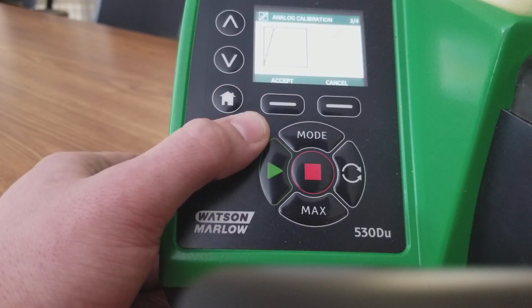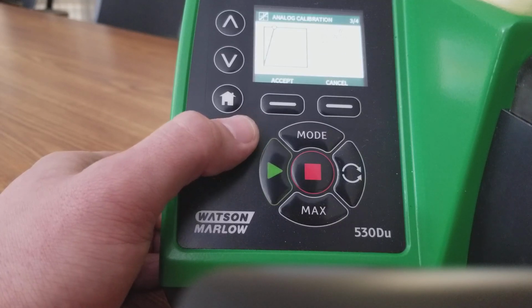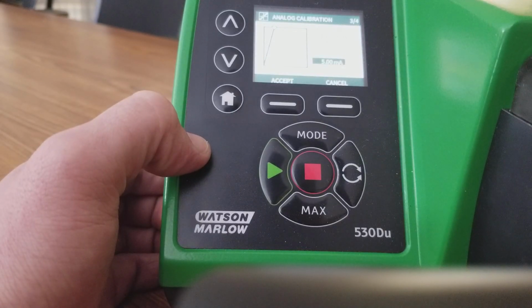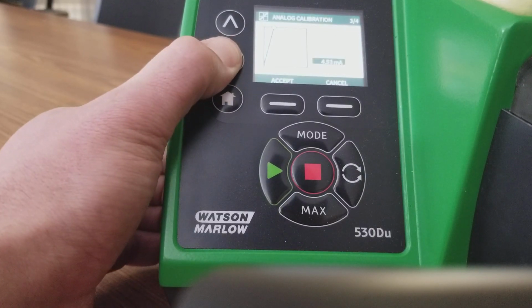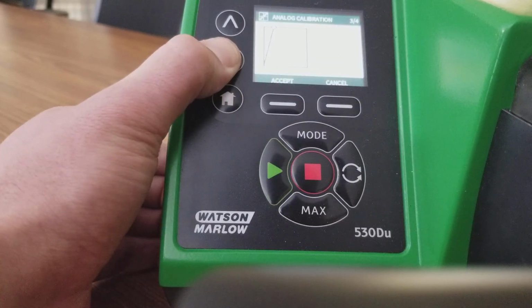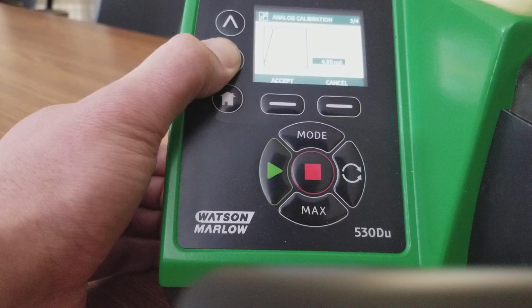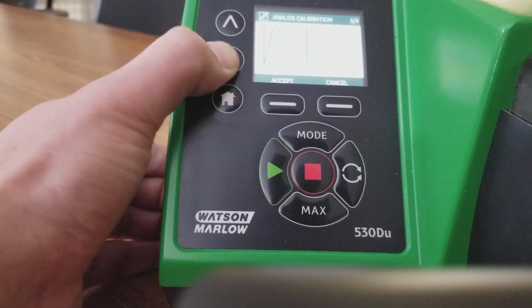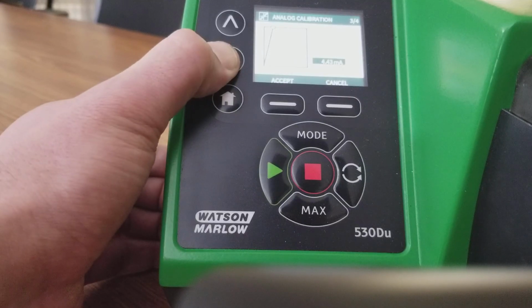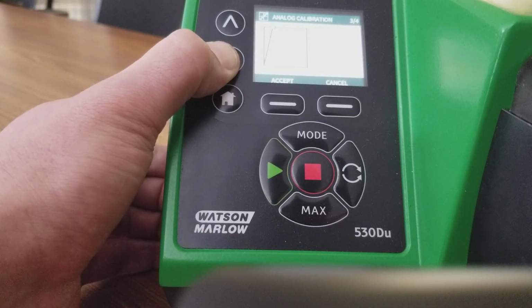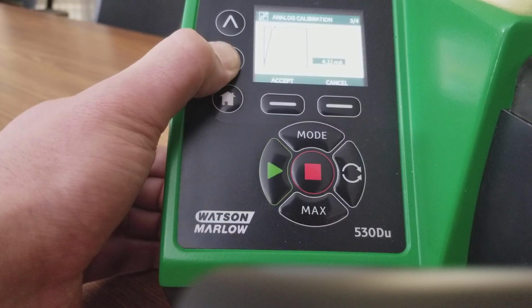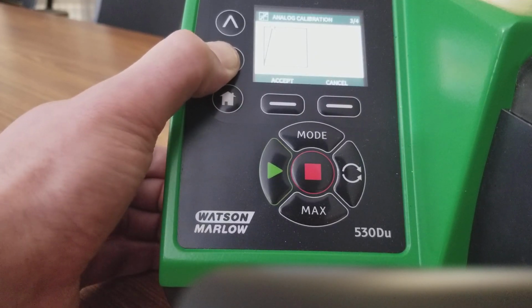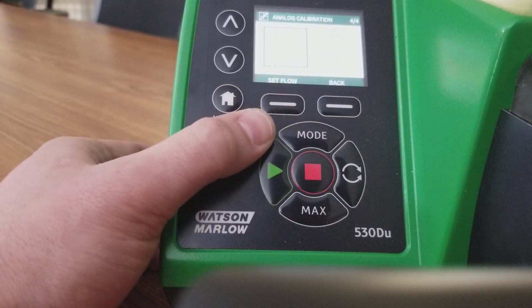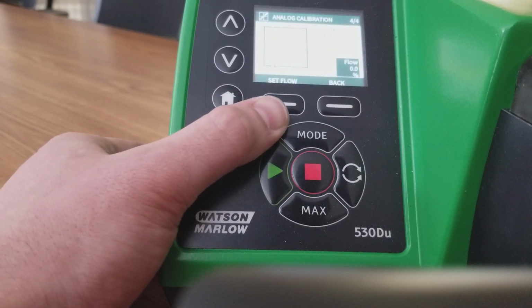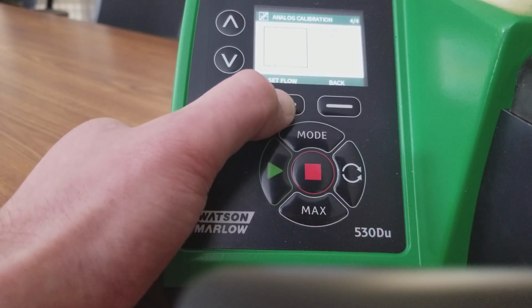The next one is where all of the problems have been coming in with the red screen of death, because from factory they come at 5 milliamps. That needs to be brought down to 4 milliamps. All the issues that Jeff and everyone else were having were due to this portion not being calibrated properly. Once we select that 4 milliamps, we can hit accept. At this point, we will want the 0 flow because 4 milliamps is our 0 percentage.